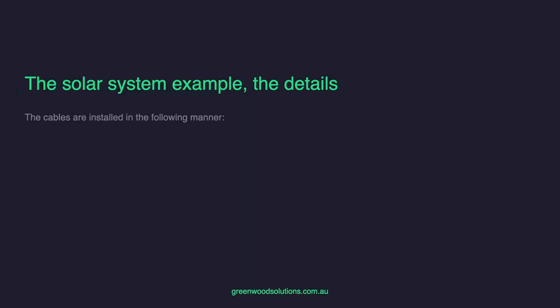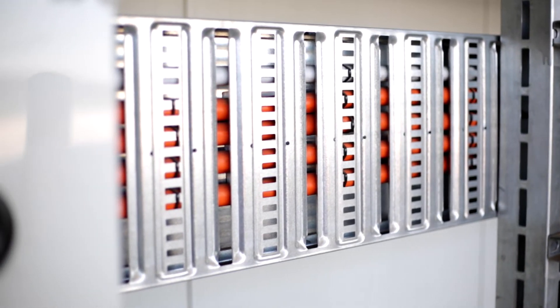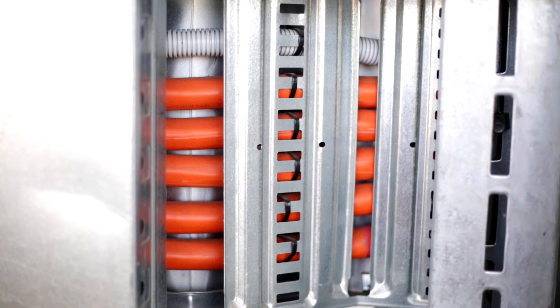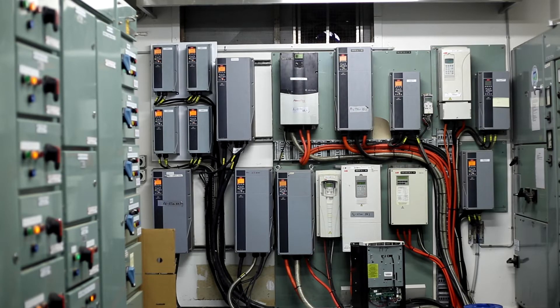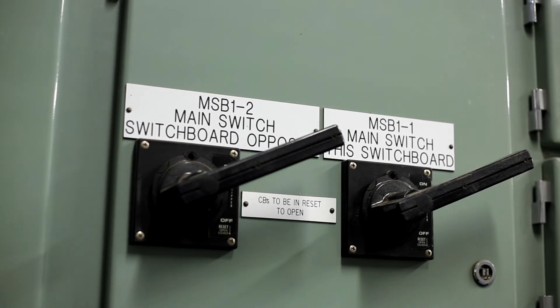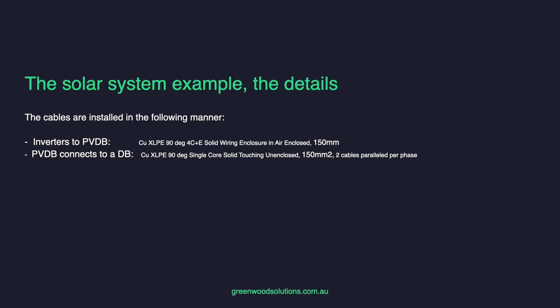The cables are installed in the following manner — this is very important. The inverter to the PVDB is in copper, XLPE, 90 degree, 4-core plus earth, solid wiring, enclosed in air — 150mm enclosed cable. The PVDB connects to a DB in copper, XLPE, 90 degree, single core, solid, touching, unenclosed, 150mm, with two cables paralleled in this situation.